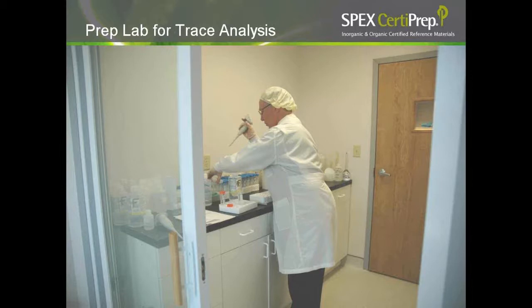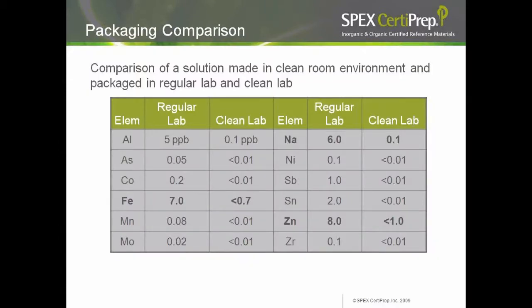This is a prep lab we use for preparing samples for ultra-low level ICP-MS analysis. It's not only essential to produce a quality sample using high-pure materials and a well-cleaned lab with proper storage containers — it's also essential to package and store low-level standards in a clean room. We manufactured a solution in a clean room and packaged them under two different conditions: one in a regular lab, another in a clean lab. Iron, sodium, and zinc impurities are at higher levels when stored in a regular lab versus packaged and stored in a clean lab.